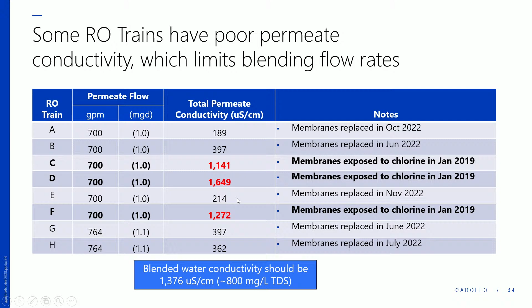So the poor salt removal is going to limit the production capacity by limiting the amount of blend, that bypass water that goes around the RO. These graphs show that RO trains A, B, E, and G that were replaced in 2022 are rejecting between 98 to 99% of all the salt, and these dates were all from 2022 to 2023.